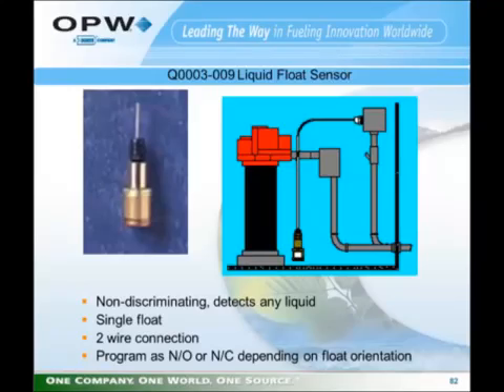This sensor is actually labeled interstitial sensor as an internal model name for OPW. Even though it's labeled as interstitial, it is used in sumps or any other portion of the installation where physically it can fit and monitor rising liquid levels. Keeping in mind that if this is used in a dispenser sump and there's liquid in the sump and it's wintertime and that liquid freezes, it could freeze and hold the magnet in place where the sensor would not function normally.